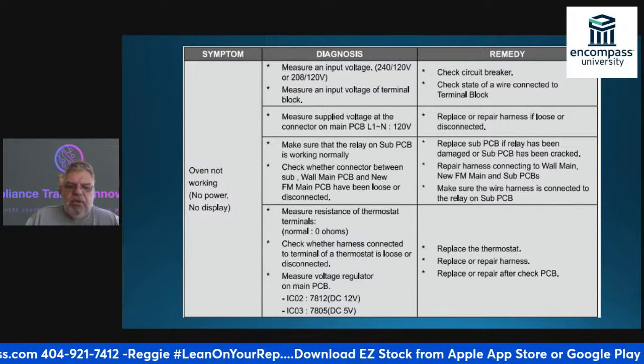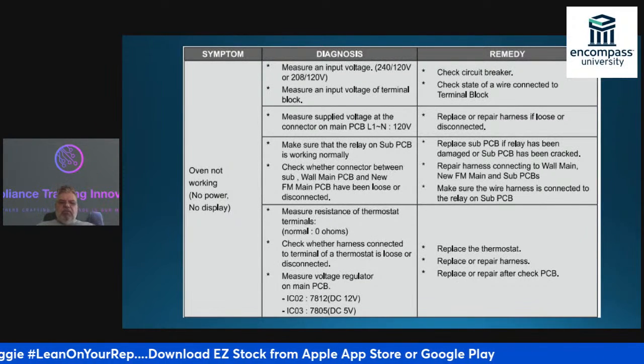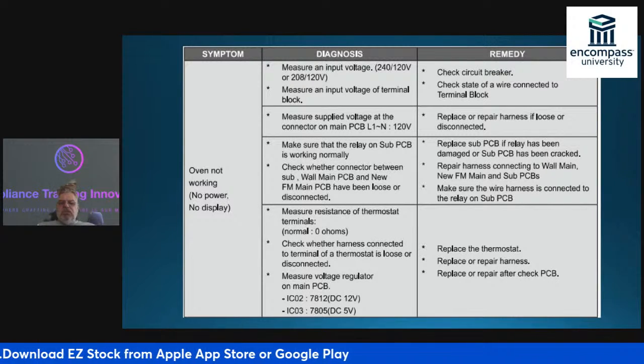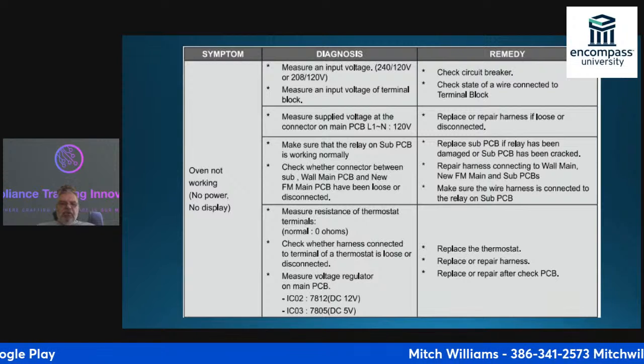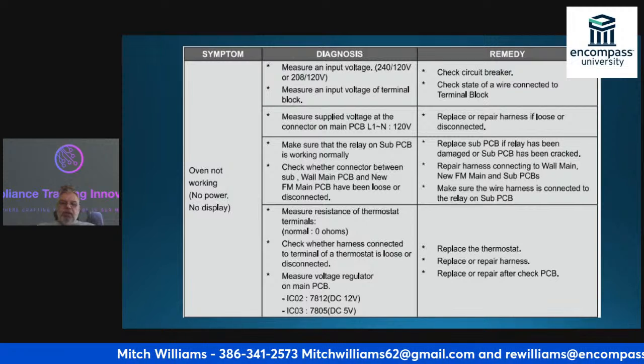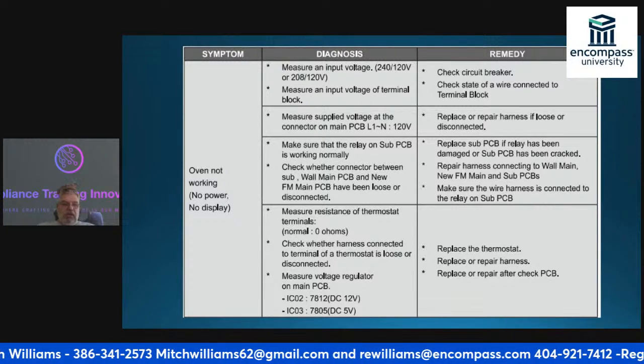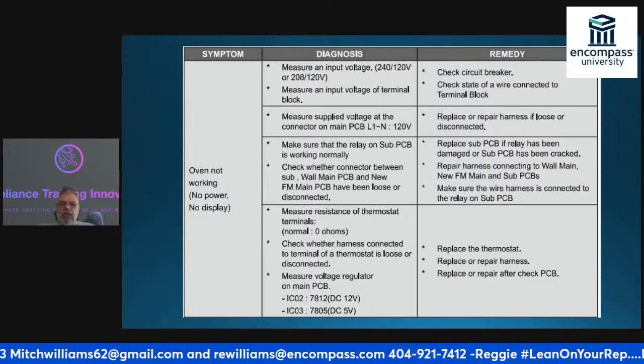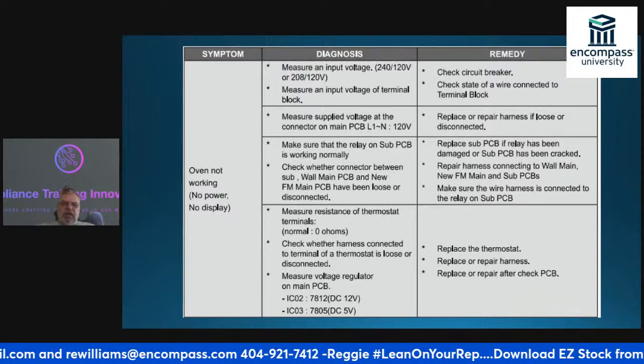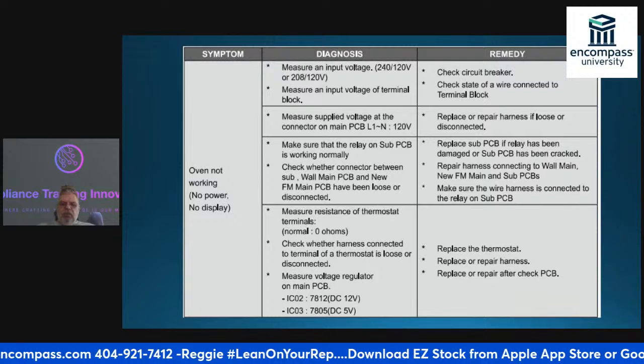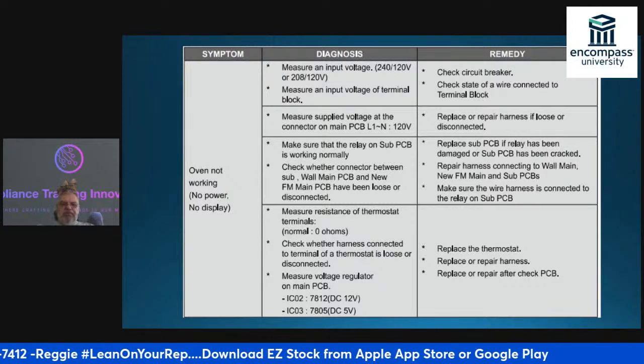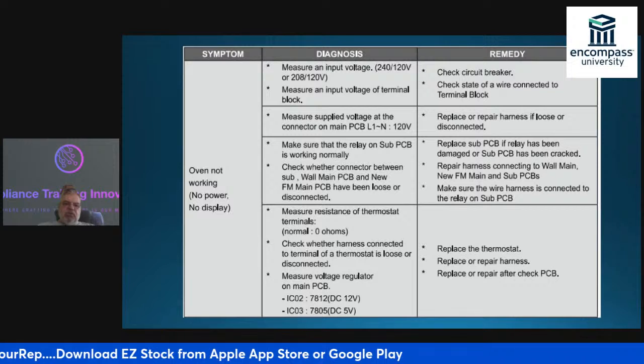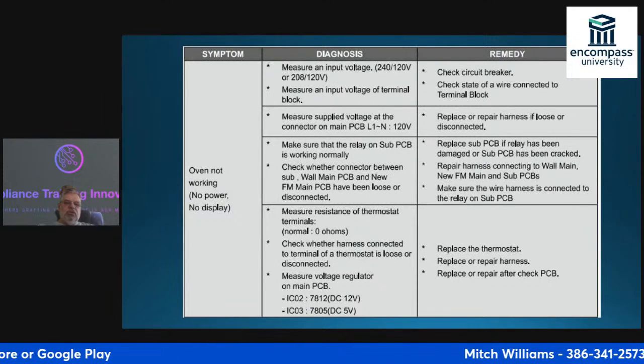I'm going to measure resistance of my thermostat terminals. Normally it's 0 ohms. If the thermostat's bad, I'm going to have to repair the harness - I'd tell you to replace it. If I have power to the thermostat, I'm going to have to do something to the PCB. So I'm going to check the harness to make sure the terminals aren't loose or disconnected.